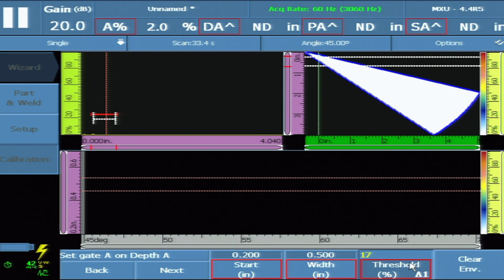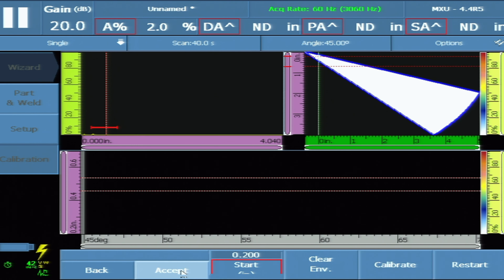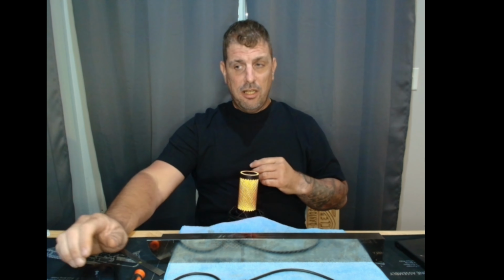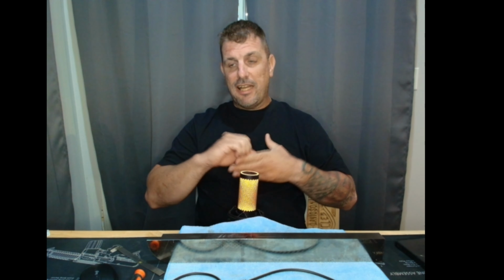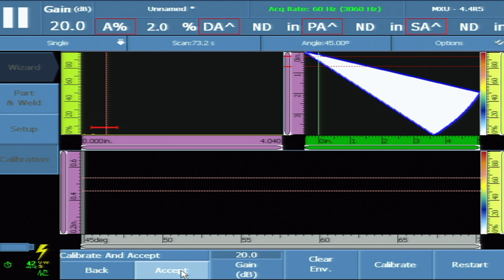For the threshold, we're going to put the threshold down to 10, and I'll tell you why. I put my gate at 10 because I don't like adding any gain when I'm calibrating. I want the machine to be at the lowest gain it brings up, which is 20. And I don't want the machine to add or take away any kind of gain. I want to leave that till when I do my TCG, so everything falls in and I don't have a whole bunch of gain in there. So we're going to go ahead and clear envelope. You're going to scan over your half-inch hole.